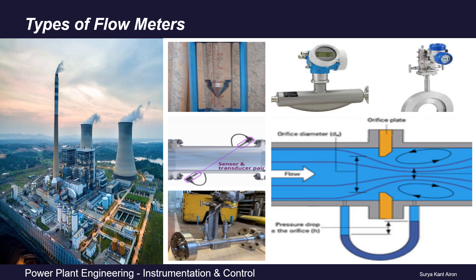In any industry, we may come across various kinds of flow measuring instruments depending upon the application and the medium — that is, the fluid being measured. For example, for conductive flows we may choose electromagnetic flow meters. Ultrasonic flow meters are highly accurate, but if the area is prone to high vibrations, we may not choose them. Similarly, a vortex flow meter may not be suitable for pulsating flow. To select the most suited flow meter for your process, you must have knowledge of its basic principle.